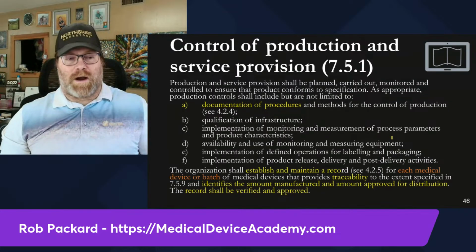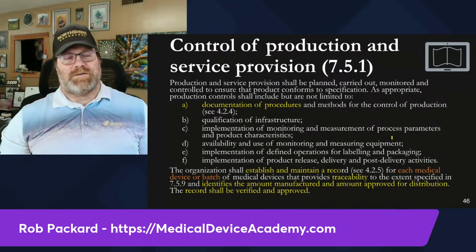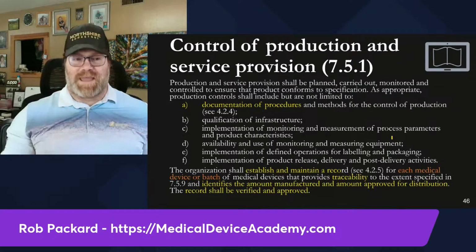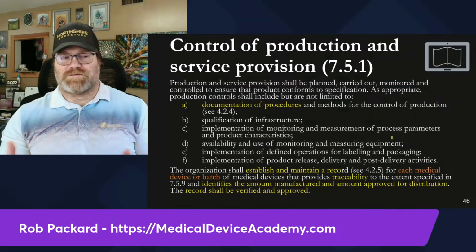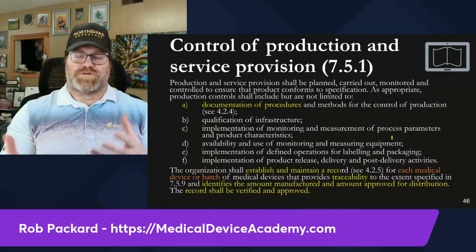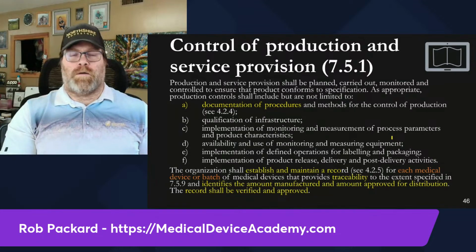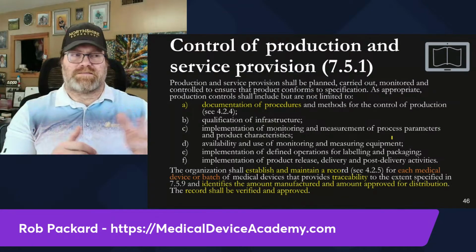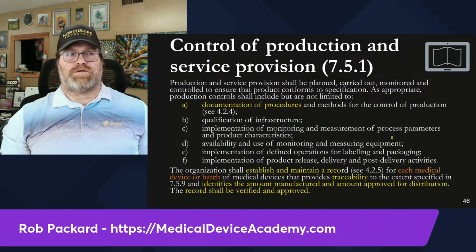If you are required to provide that extensive traceability for implants, then you have to do that. But if you are doing something where the whole entire lot of 1,000 parts is the same, then you need it for the batch. And so you might be doing a statistical sampling of the batch. So that you look on an AQL chart, you might do normal sampling, a 1.0, and you pull this number of samples. It could be a Z1.4 plan. It could be a Z1.9 plan. So depending on that, it's going to tell you how many samples and how large the lot was. You'll know what you have to pull, and then you would sample those parts.